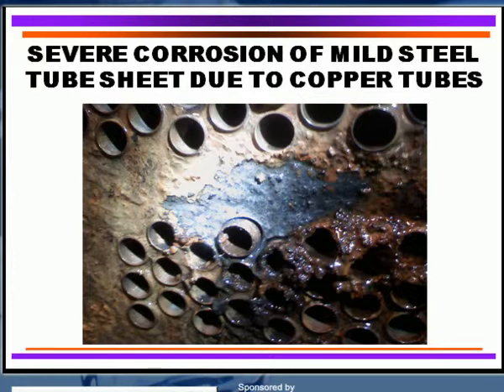Here's an example of really serious pitting attack between the actual tube and the tube sheet. In some cases you have the tube extending further out than it would normally be, but you can actually have penetration, corrosion product buildup, plugging in the tubes, and possible leaks between the tube and the tube sheet, and that would mean that the refrigerant would be lost.